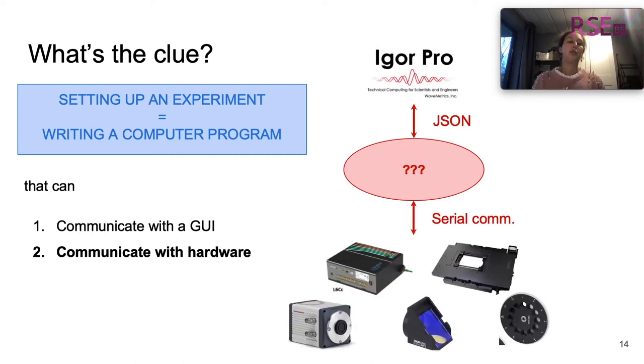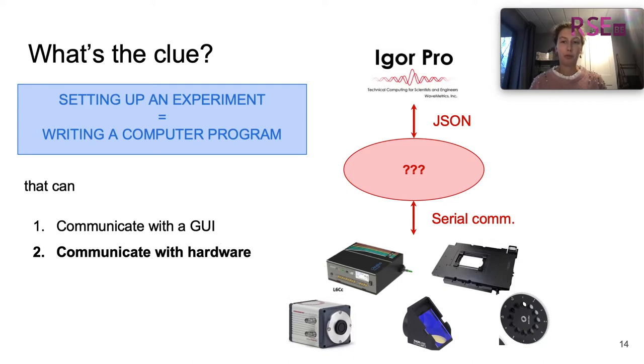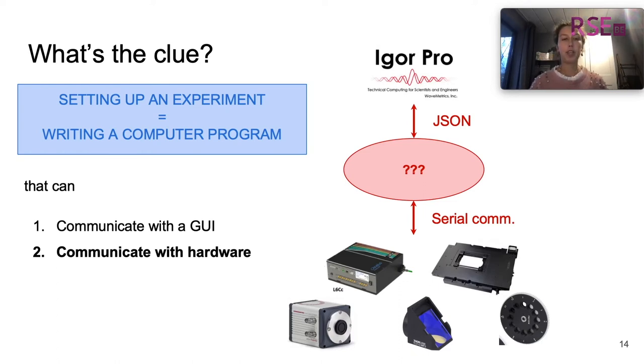The user interface then polls to see if data is available. Secondly, our computer program should be able to communicate with hardware. There are several kinds of hardware in the microscope — think about a stage, a camera or other detection systems, dichroic mirrors, filter wheels, to name but a few. Communication with the hardware happens via COM ports, so this is serial communication. Sometimes a DLL is provided written in C by the manufacturer of the hardware, so our program should be able to support all these kinds of hardware and their features.